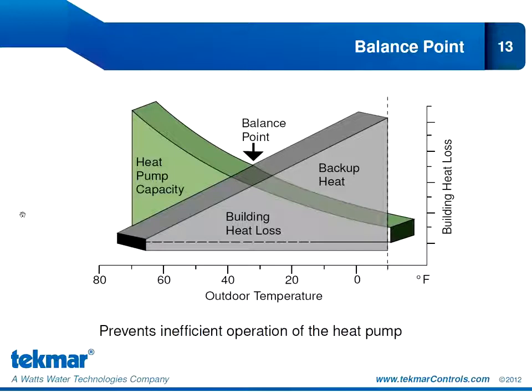Balance point, as I mentioned earlier, is when an air source heat pump loses its efficiency advantage. Another way of saying this is its coefficient of performance approaches 1. In other words, the energy it takes to operate our heat pump is the energy we're getting out of our heat pump. So there really is no use in using our heat pump beyond this balance point setting. If the outdoor temperature drops below that setting, the 557 will not bring on the heat pump, but will use the backup heat source instead.